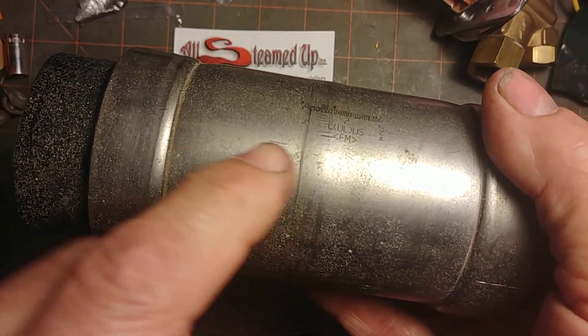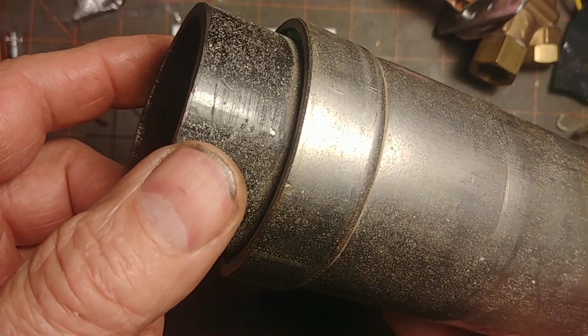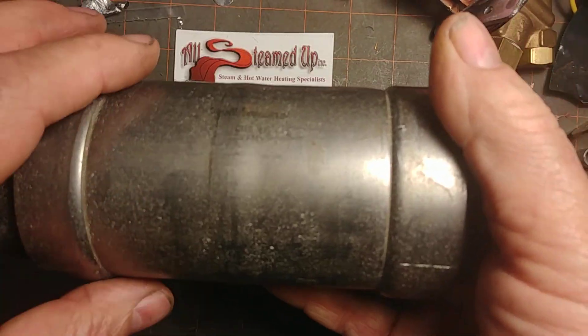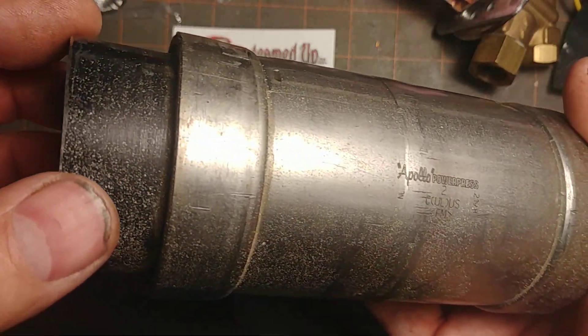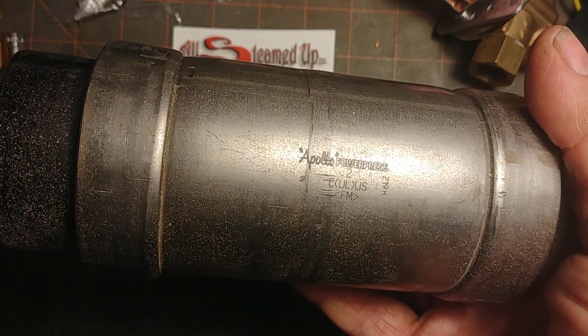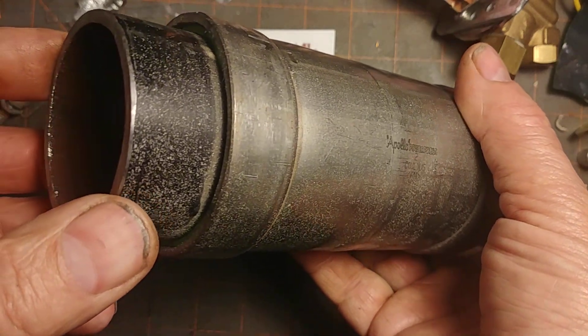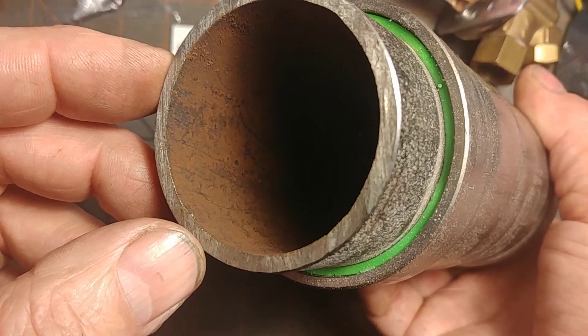So they cut about here — this is the newer material — and this had to be cut out because they didn't take into account the pitch. That's the trouble with this product: it tends to allow misalignment and allows the misalignment to continue. So unless you fix the underlying problem, this solves the immediate problem of a leak but does not solve the underlying cause of the leak.